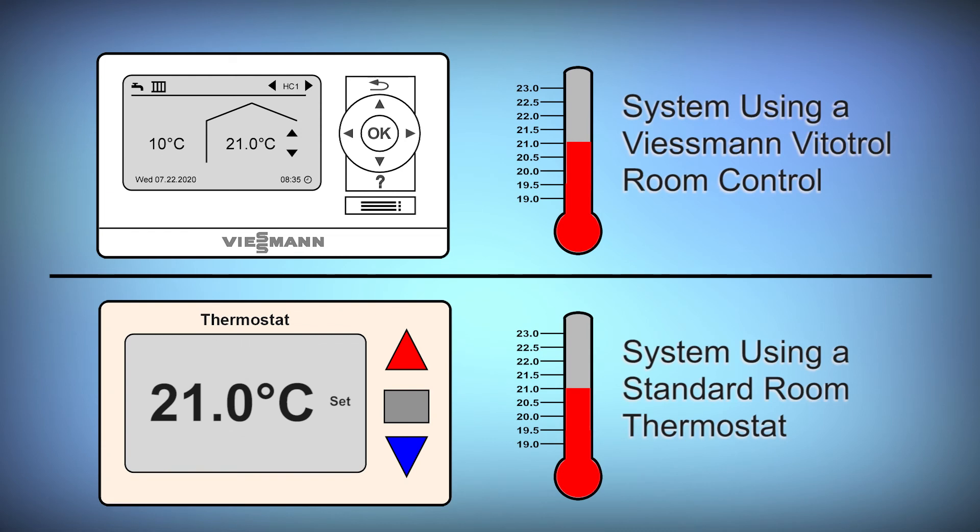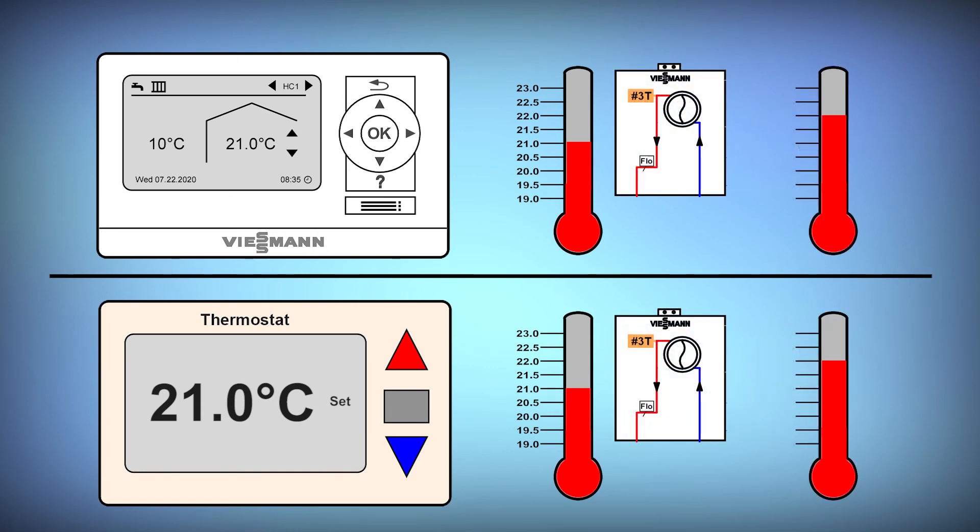When we compare controlling room temperature with a traditional thermostat to a Viessmann Vitotrol room control we can see that when using a room thermostat the differential built into the thermostat plus the reaction time of the system means that there's a fairly large room temperature swing as well as a fairly large water temperature swing. Whereas because the Vitotrol is communicating in real time with the boiler the boiler can react to load changes in the space quickly and efficiently reducing the swing in room temperature and the swing in system temperature.